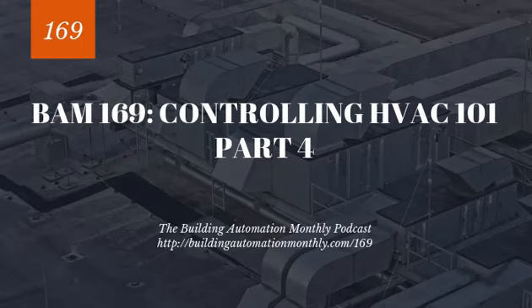Or we're taking a more inclusive approach to controlling it, where we're actually concerned about the flue and the oxygen percentage, and we're concerned about the dampers in the room that the boiler's in, so it has an oxygen feed and an exhaust and all that. I will tell you though, in the majority of my experience, we are just simply sending an enable and doing burner control.